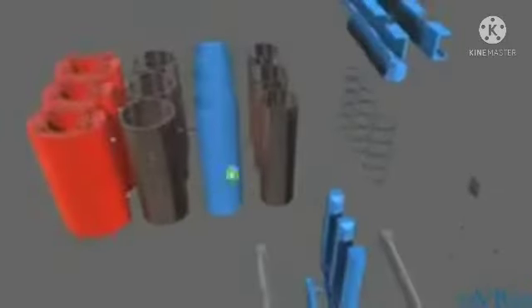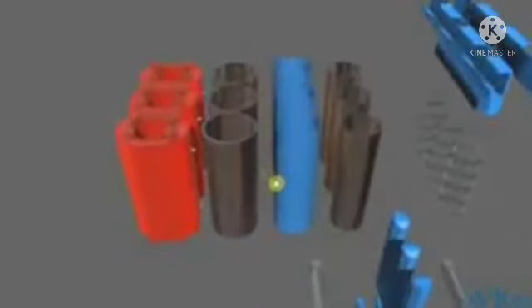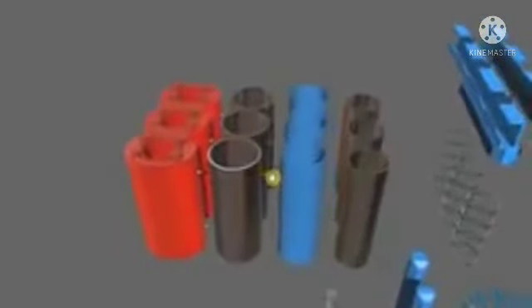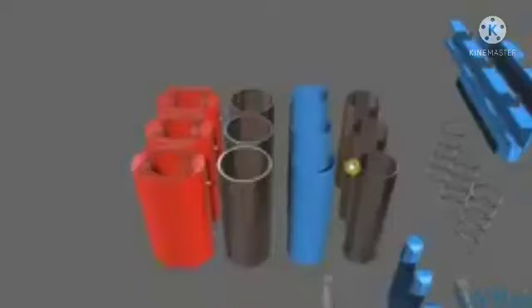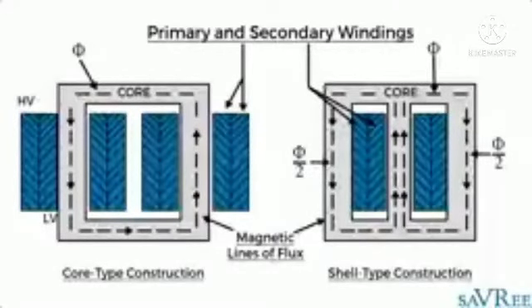So there's the core, and we can see here all of these circular items are going to be installed onto each of the limbs. Remember, one limb is one phase, so this is a 3-phase transformer. And within this group, we're going to have low voltage windings and high voltage windings. The low voltage windings are going to be installed closest to the core. So they're going to be wrapped around, or very close, should I say, to the core. Immediately after the low voltage windings, we're going to have high voltage windings.